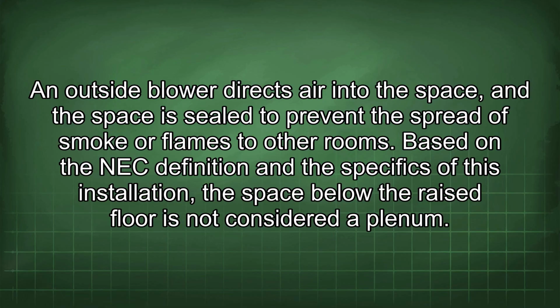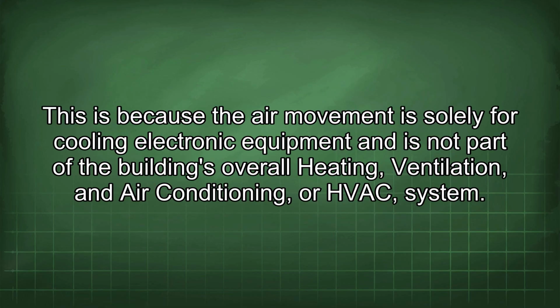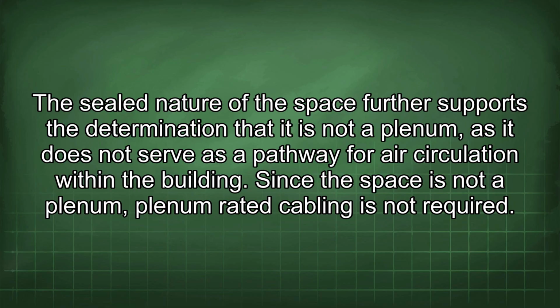Based on the NEC definition and the specifics of this installation, the space below the raised floor is not considered a plenum. This is because the air movement is solely for cooling electronic equipment and is not part of the building's overall heating, ventilation, and air conditioning, or HVAC, system. The sealed nature of the space further supports the determination that it is not a plenum, as it does not serve as a pathway for air circulation within the building.